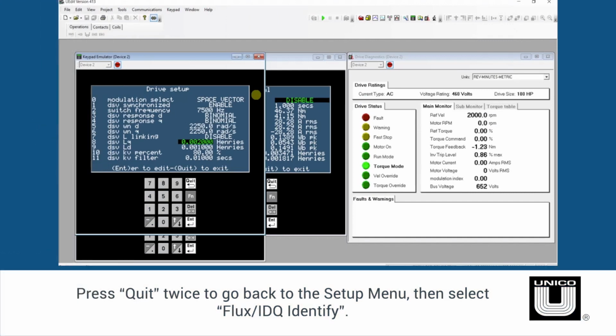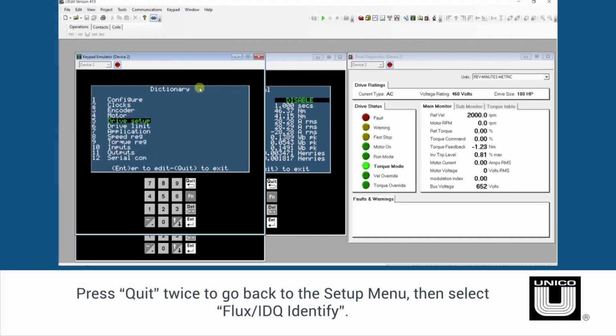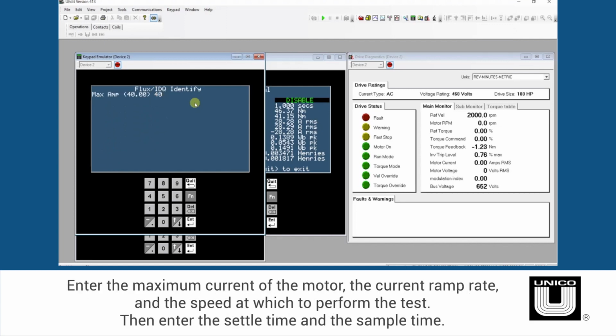The next step is to begin the flux mapping process. Go back to the Setup menu, then select Flux IDQ Identify. Enter the maximum current of the motor, the current ramp rate, and the speed at which to perform the test. Then enter the settle time and the sample time. The default values for these are usually okay.